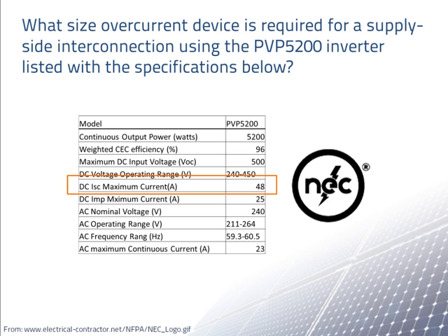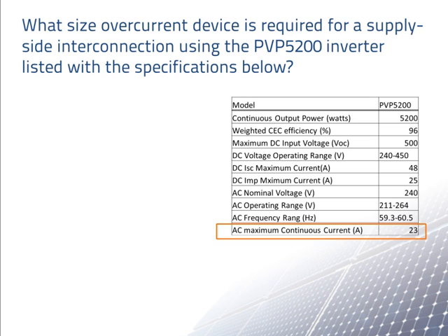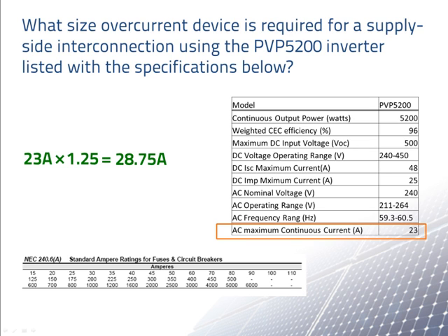We see that the last row of this chart lists AC maximum continuous current as 23 amps. We use this maximum current to find the overcurrent rating by finding 125% of the maximum current. 23 amps times 125% gives 28.75 amps.